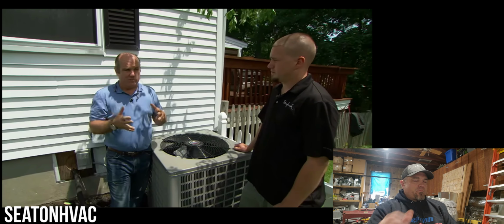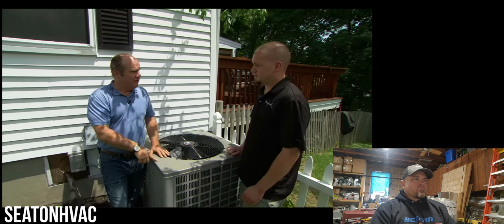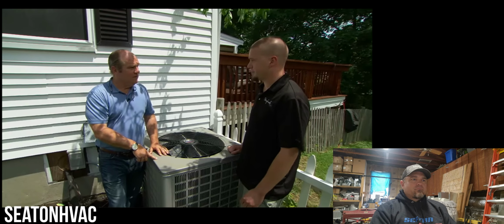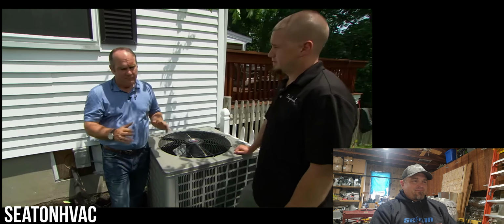Now, how big is this house? Wow, mine's only 1,300. I'm hoping that they actually did the real calculations instead of doing these rule of thumb things. 500 square feet per ton. That's a rule of thumb that a lot of hacks use. So let's see what they end up doing here. 1,300. There's a chance we needed only like a 2.5 ton. This is a 4. Now you ordered the system originally, right? Yeah, the guy that put it in said it would be plenty big. Plenty big. We hear this all the time.